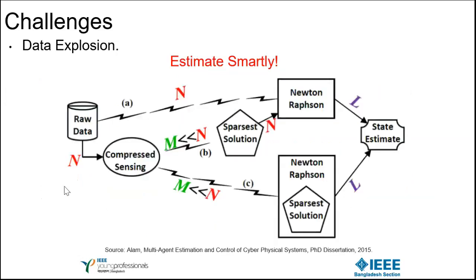So once we have the compressed data, how do we use it? One typical case is using measurement data in a power system to estimate the state. We collect measurements like real and reactive power consumption, real and reactive power flow over the grid, and sometimes voltage magnitude and angles. The main goal is to get node by node, bus by bus voltage magnitude and angles - these are the unknown values we want to estimate. There's a numerical approach called Newton-Raphson used for this.